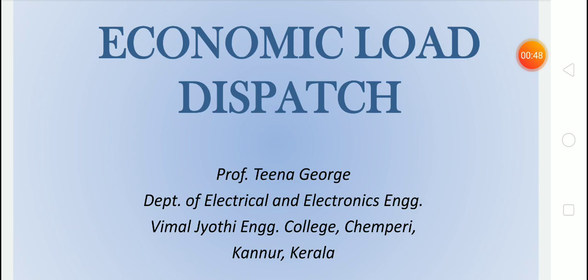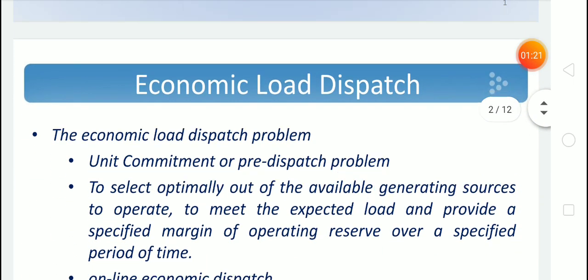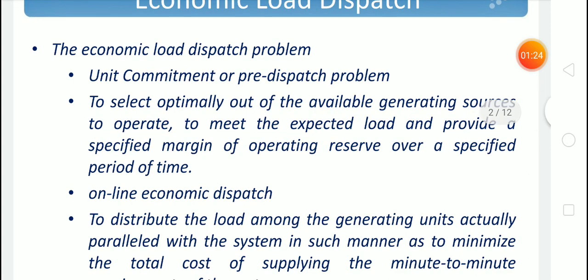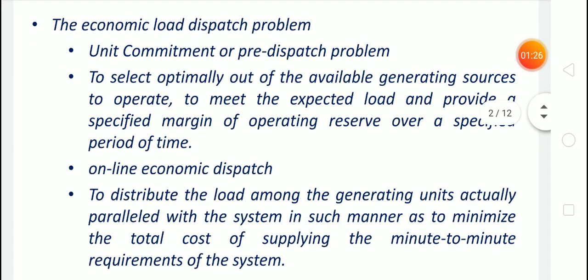Economic load dispatch mainly consists of two problems: the unit commitment problem and the online economic dispatch or cost minimization problem. The unit commitment problem is a pre-dispatch problem — we use load data from previous years to schedule generation. The online economic dispatch problem is done according to current data. So the two problems are unit commitment (pre-dispatch) and online economic dispatch.